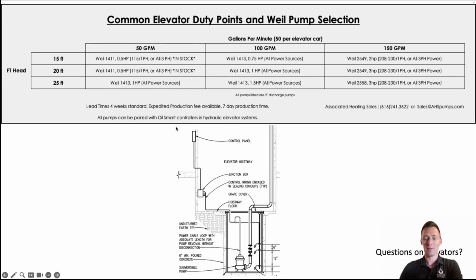I do have a chart if you are looking to specify a Weil pump for your elevator system, and it asks you your duty point. So how many feet of head are you pumping against and how many gallons per minute? Keeping in mind this is per elevator car, 50. So these are the most common model numbers that are used for a Weil pump in that system.